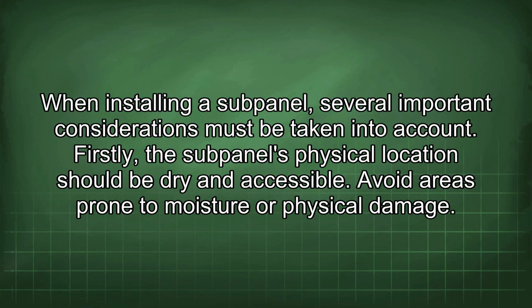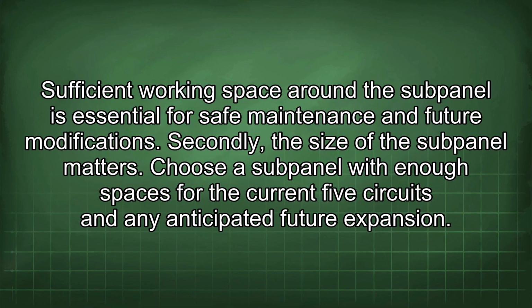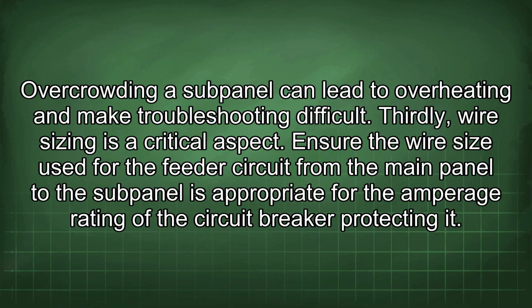When installing a subpanel, several important considerations must be taken into account. Firstly, the subpanel's physical location should be dry and accessible. Avoid areas prone to moisture or physical damage. Sufficient working space around the subpanel is essential for safe maintenance and future modifications. Secondly, the size of the subpanel matters. Choose a subpanel with enough spaces for the current 5 circuits and any anticipated future expansion. Overcrowding a subpanel can lead to overheating and make troubleshooting difficult.